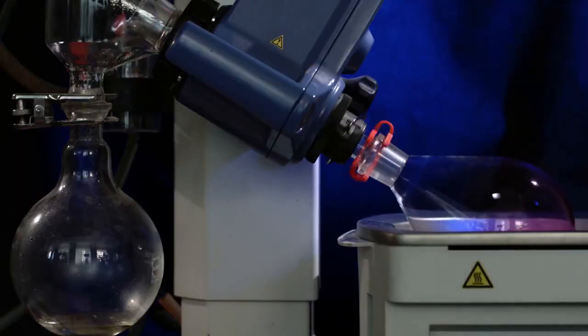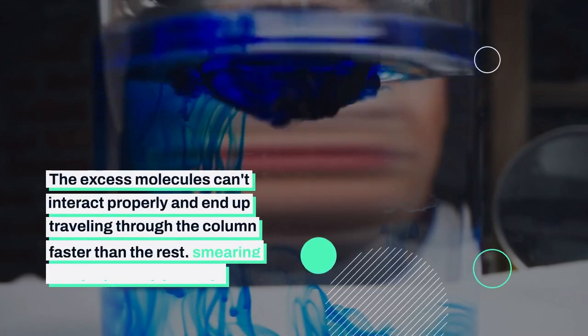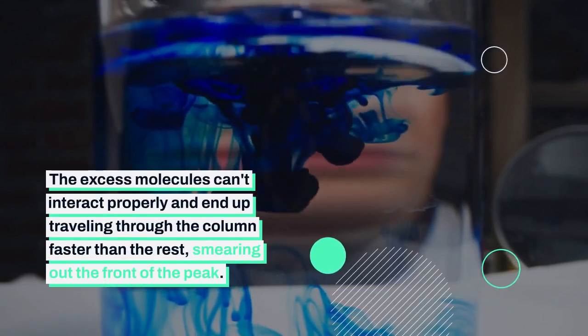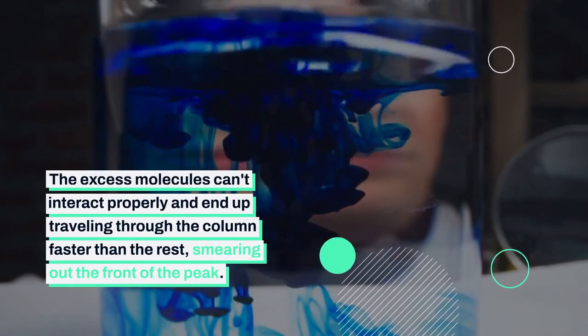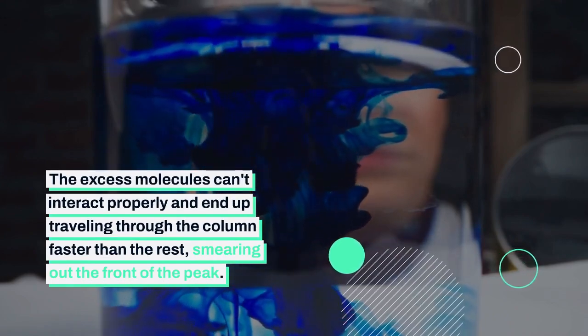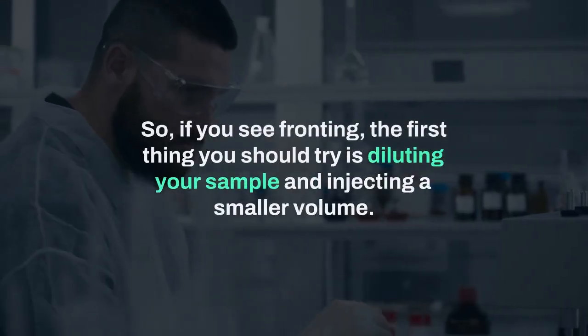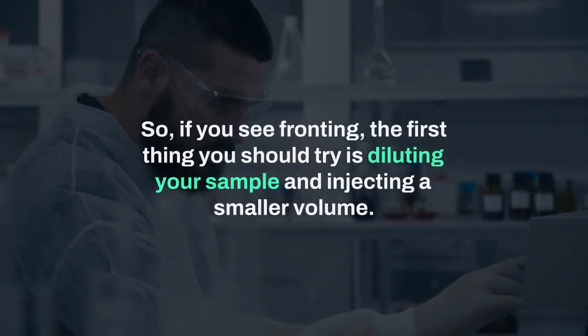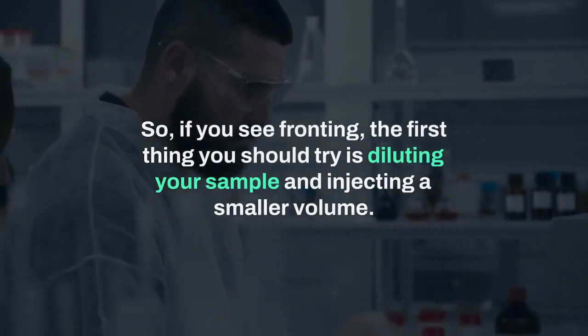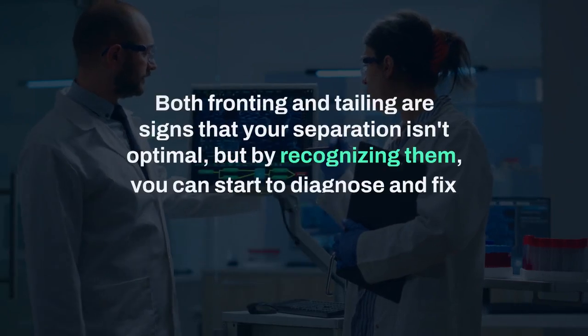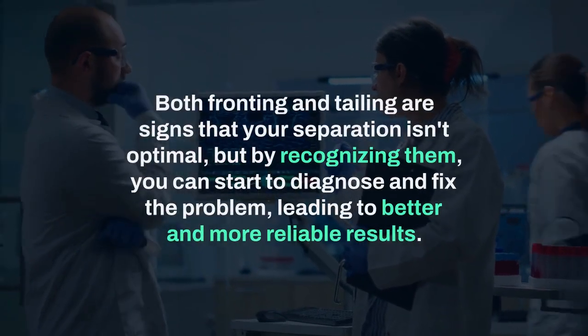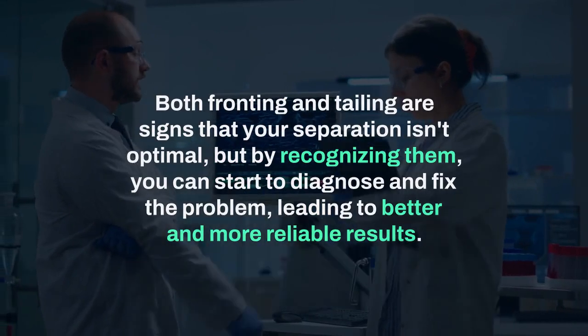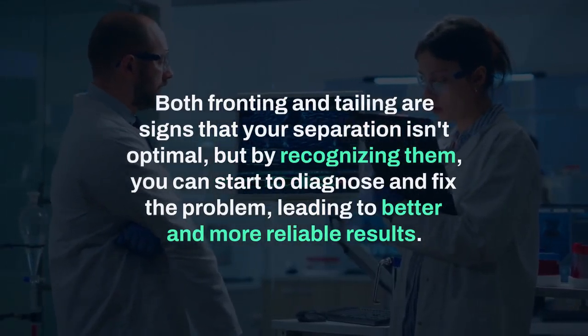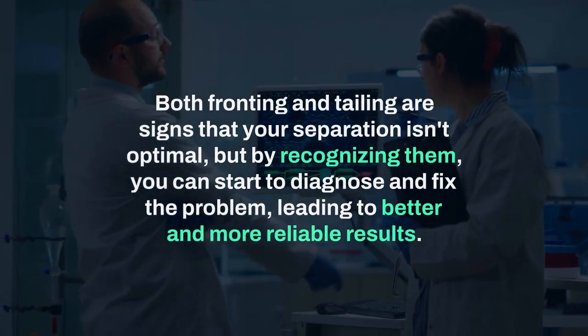The stationary phase becomes saturated, and it simply can't handle the high concentration of the analyte. The excess molecules can't interact properly and end up traveling through the column faster than the rest, smearing out the front of the peak. So, if you see fronting, the first thing you should try is diluting your sample and injecting a smaller volume. Both fronting and tailing are signs that your separation isn't optimal, but by recognizing them, you can start to diagnose and fix the problem, leading to better and more reliable results.